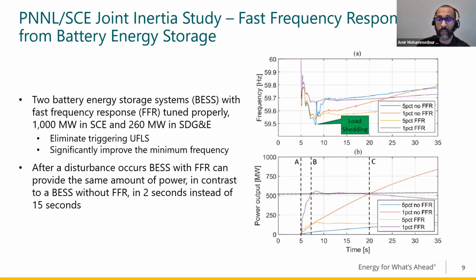The study showed that by including 1,000 megawatts of storage in SCE's system and 260 megawatts in San Diego, with fast frequency response capability, you can potentially eliminate triggering under frequency load shedding and significantly improve the minimum frequency observed during large disturbances. Plot A on the top right shows system performance with different droop values, with and without FFR capability. In blue, with a smaller droop gain and no FFR capability, system frequency can potentially reach UFLS thresholds. In purple, with a larger droop gain and FFR capability, the minimum frequency can be significantly improved.